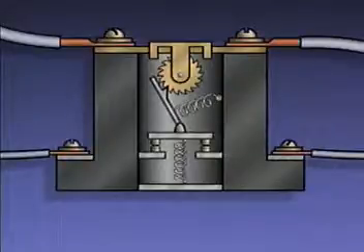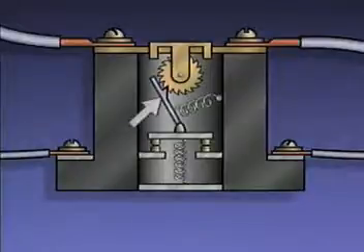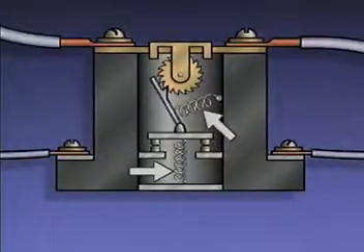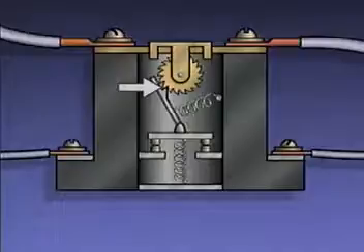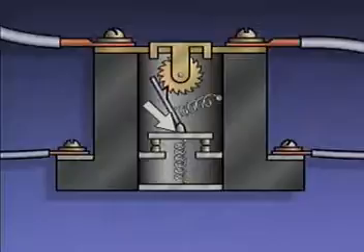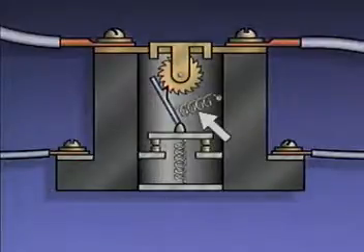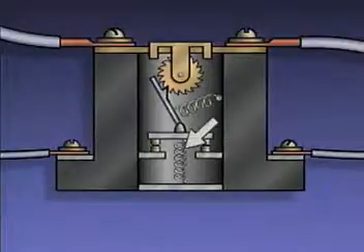From this angle, we can see the top of the ratchet wheel here. We can also see that the solder pot has a mechanical linkage, movable contacts, which are in the motor controller's control circuit, and 2 springs. The ratchet wheel, which is set on the rod, holds the mechanical linkage in place. The movable contacts are attached to the mechanical linkage, and the stationary contacts are positioned in the casing of the overload device. The linkage spring holds the mechanical linkage against the ratchet wheel, and the contact spring pushes against the movable contacts.